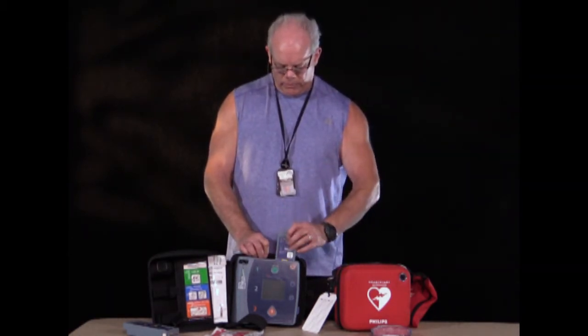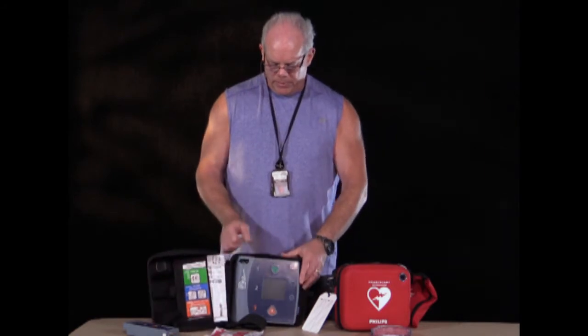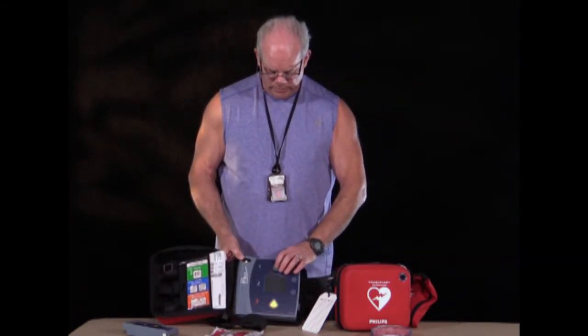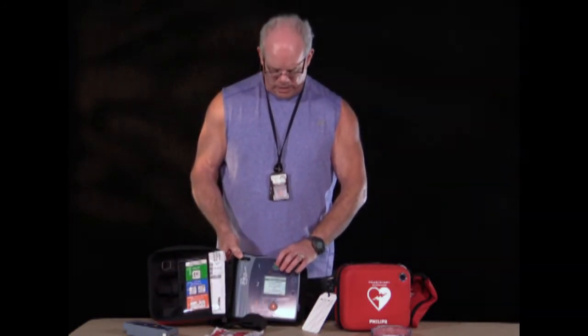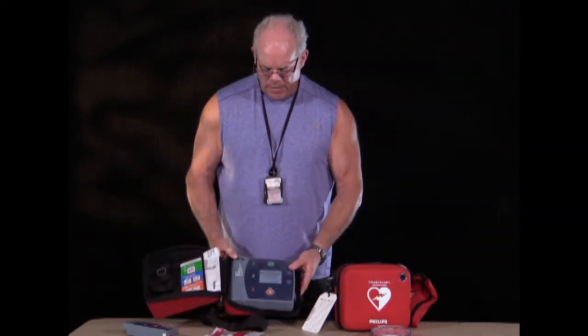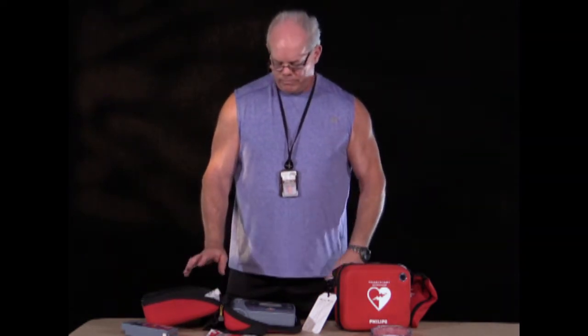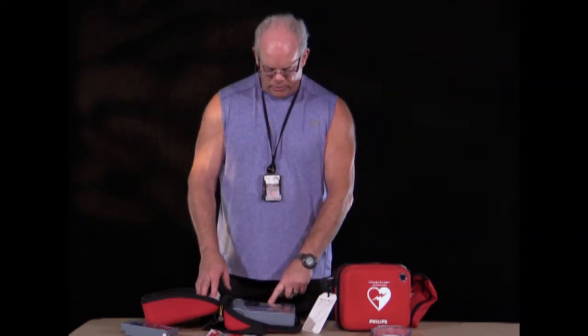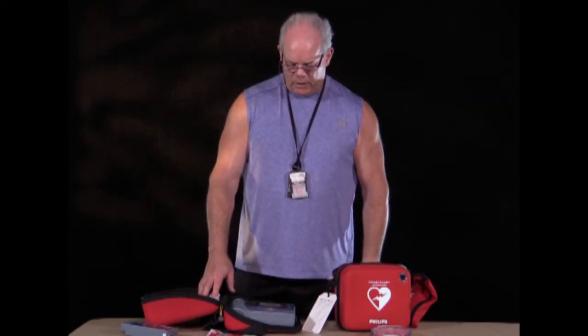So this one is good for a while longer. And so typically the batteries are good for, now it's going to come back on, I'm going to turn it back off. Oh, it just blinked on. So the batteries are good for anywhere from 4 to 6 years. The pads are good from anywhere from about 2 years to maybe 2.5 years. So we need to make sure that these are all checked properly and are ready to go.